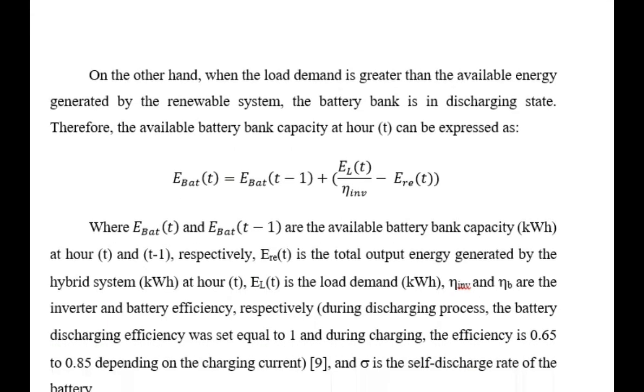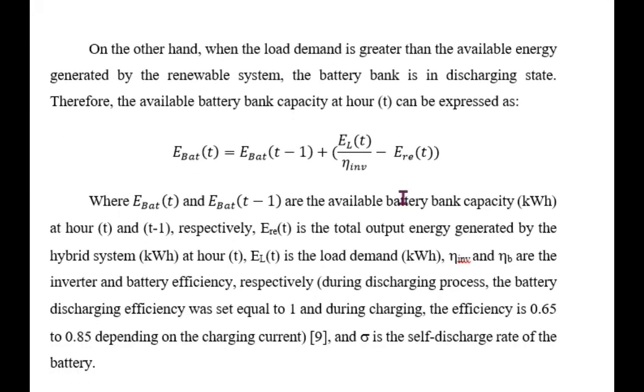Similarly, for discharging of the energy, when there is an insufficient amount of energy to meet the load demand, the battery new energy at time t will be previous energy minus the deficient amount of power that has to be provided to the load. So E load divided by inverter efficiency minus E renewable energy that is provided by the renewable energy sources. So that will be the deficient amount of power. The load demand minus renewable, that is the deficient. That cannot be met by the renewable.